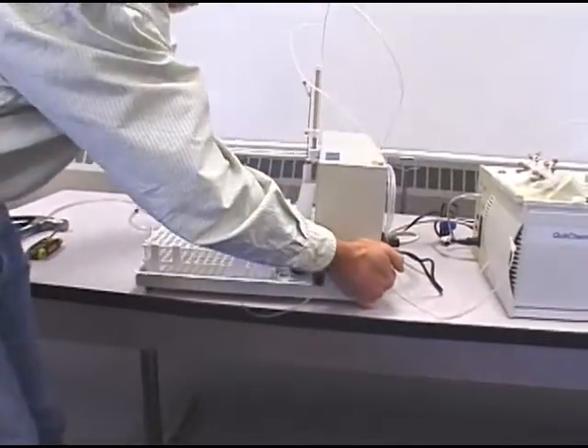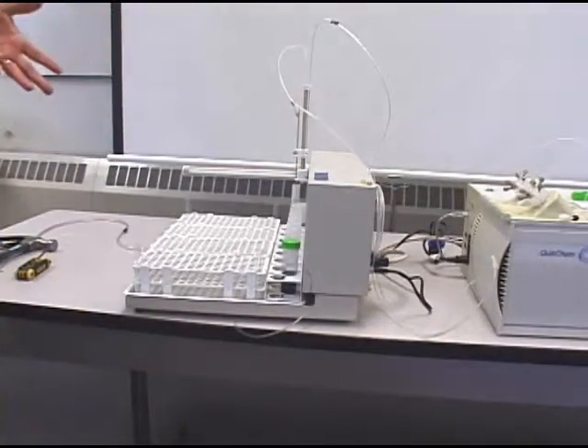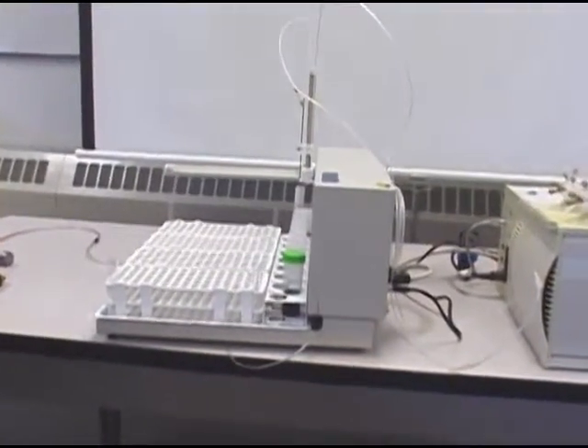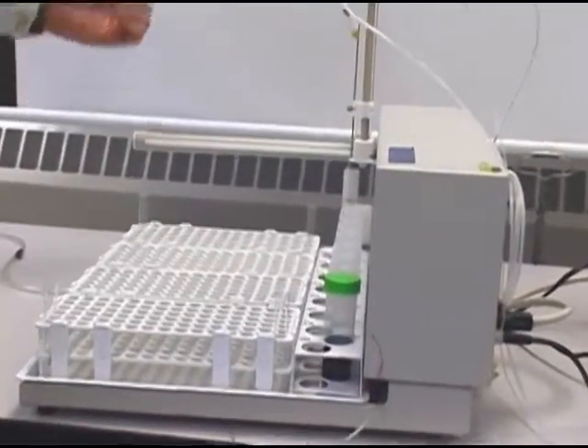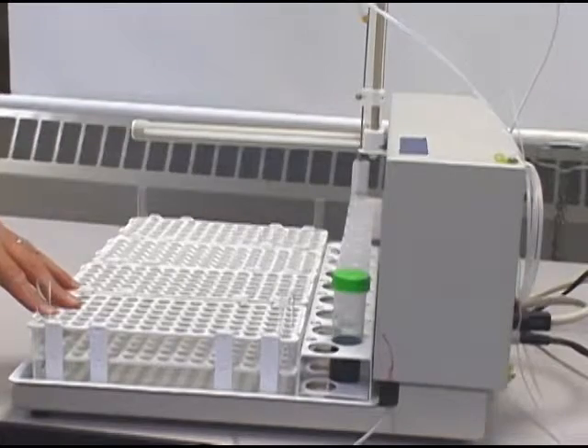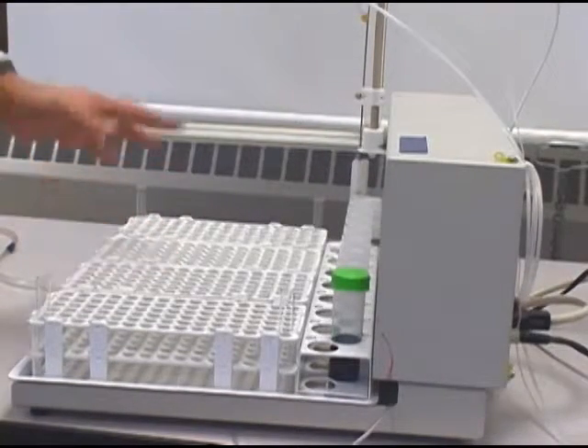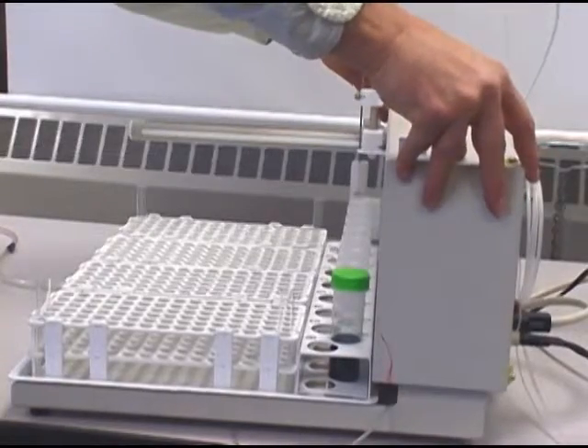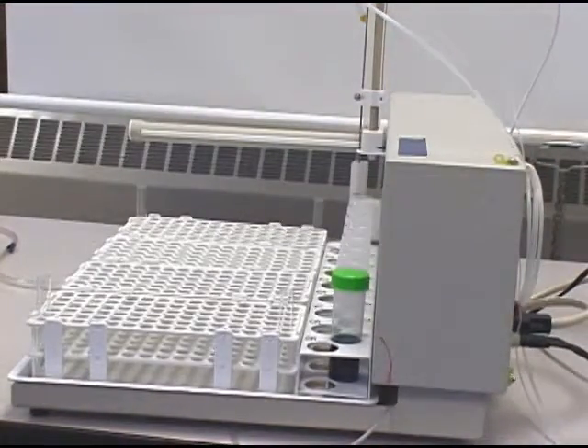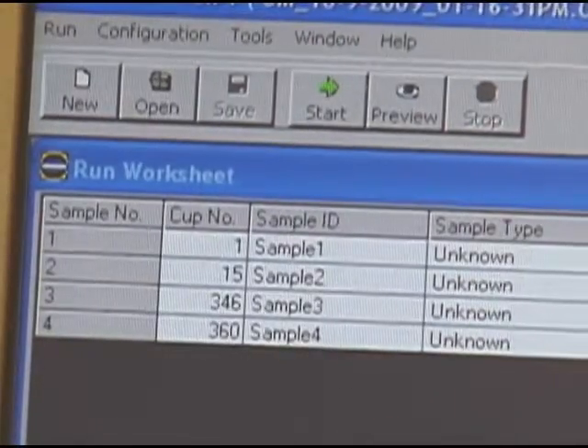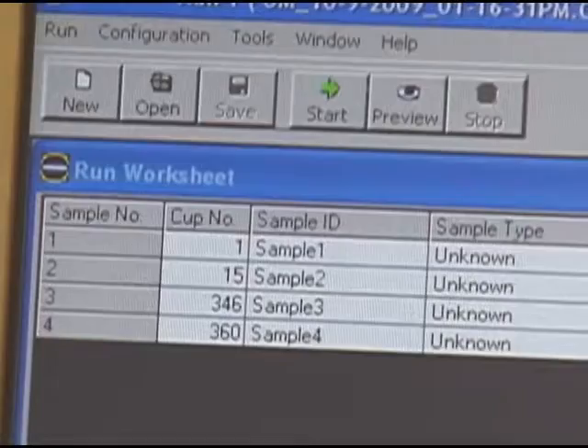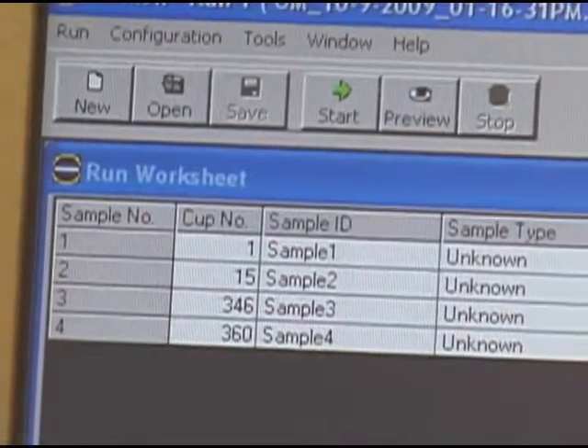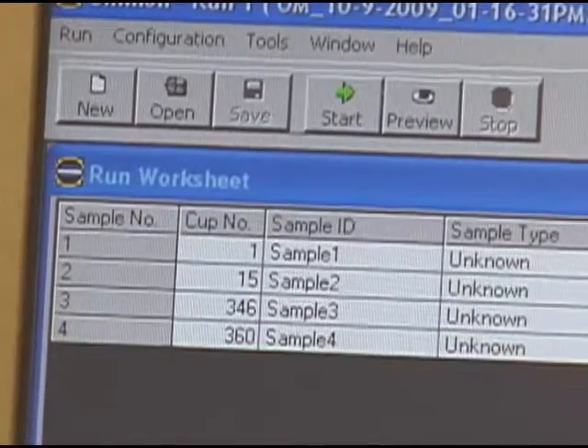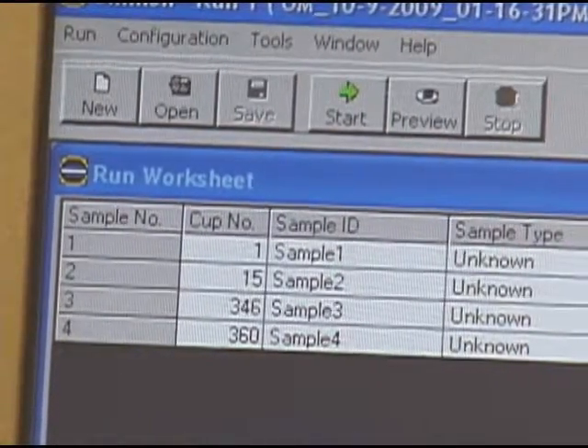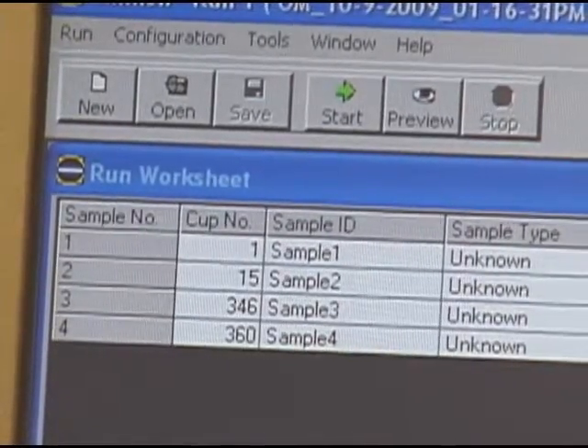And what I need to do now is run a 4 corners test on the autosampler so that the probe is sent to each of the 4 corners of the samples, and when they come to those 4 corners, I'm going to need to adjust this carriage to make sure that it fits properly in those 4 tubes. So what we have here is a program on Omnion that sends the autosampler to the 4 corners of this AXS400, which has 90 position trays. If you're using different size trays, you'll need to adjust these sample cup numbers so that it actually goes to those 4 corners.